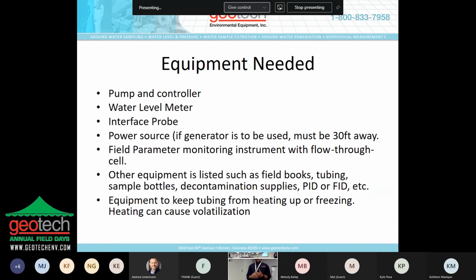Field parameter monitoring instrument with a flow through cell. This is from the EPA as well. And if you haven't seen a flow through cell before, basically what we're doing is putting our sensors in a sealed environment and we're pumping through, displacing the air volume and discharging out the top of that cell. What that does is it creates a zero headspace environment and it allows you to monitor for what we need to do next, a crucial part of low flow sampling, which is monitor for stabilization. EPA does not want this done in a bucket. It needs to be done in a flow cell, okay?